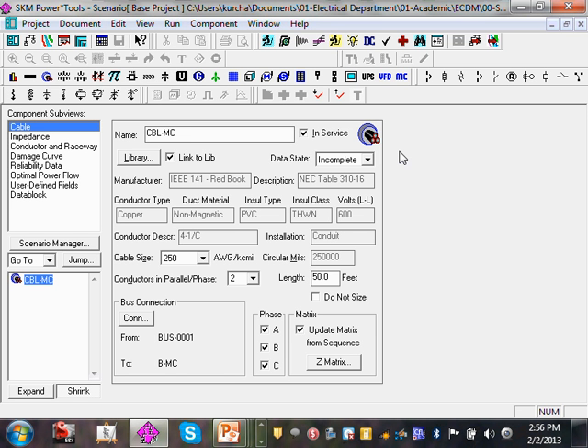And the conductors that I'm using are based on IEEE books. We have copper, non-magnetic, so we're using PVC conduit. We're using THWN rated for 600 volt, and I'm using 4 single conductor cables in a conduit. And I'm running 50 feet into the termination box. Cool? From the transformer into the termination, that's where you put the distance. Who cares about the distance? I'll give you the impedance.